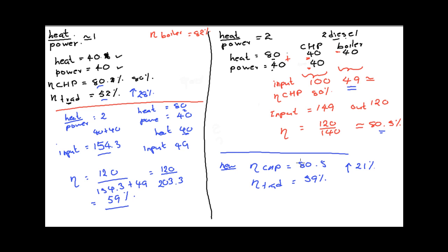At this situation, the savings have been reduced, which means the time taken for the payback period is going to increase. Therefore, when implementing a CHP system, we have to check how much energy we are going to save and in terms of money as well. Heat-to-power ratio is a very vital factor. Normally for diesel engines, the heat-to-power ratio is optimum around 1, but this can change from situation to situation. For further understanding regarding this issue, you should read section 8.4.